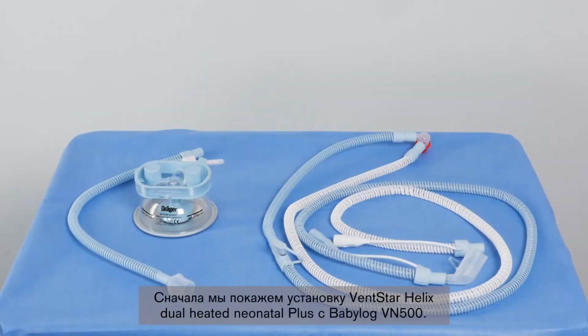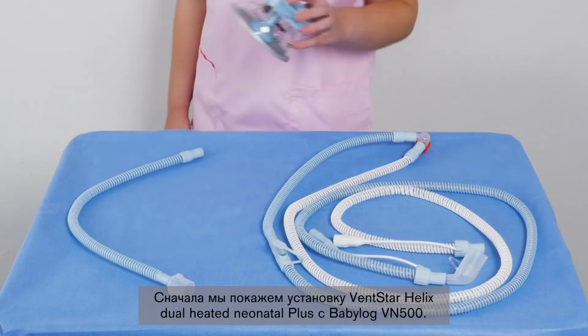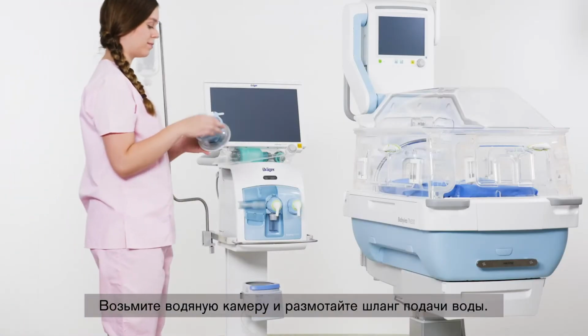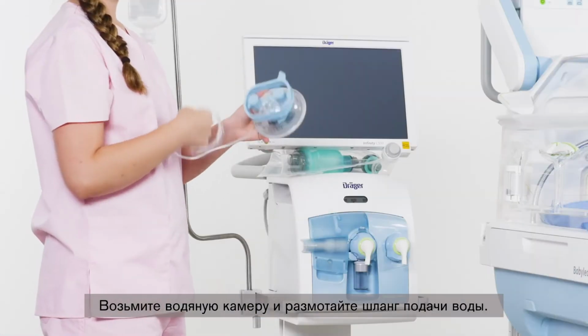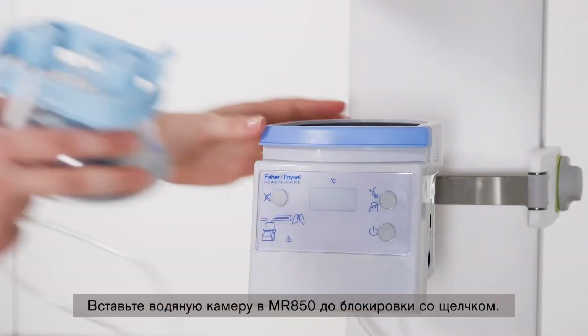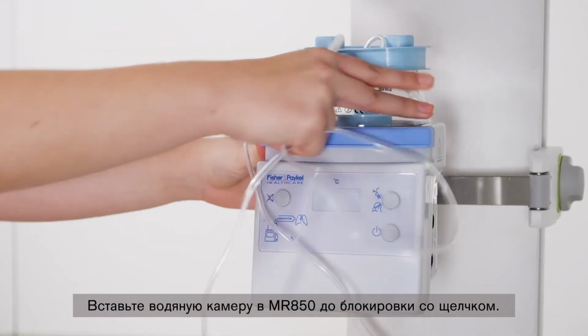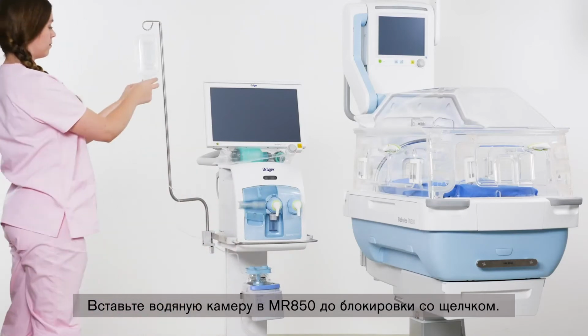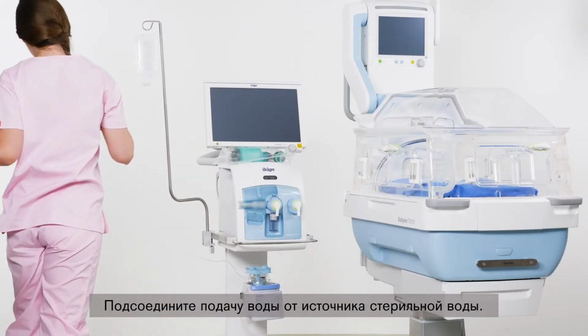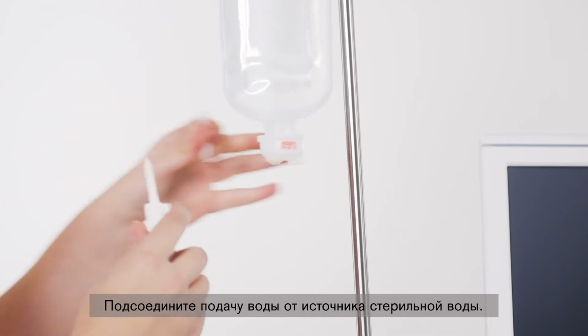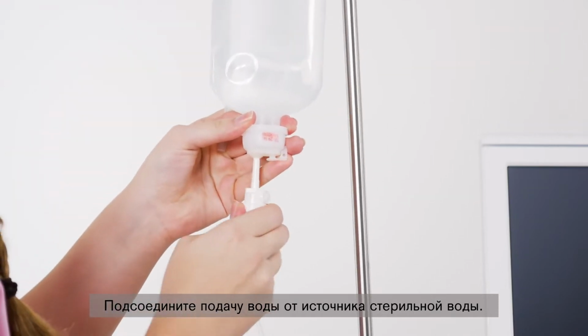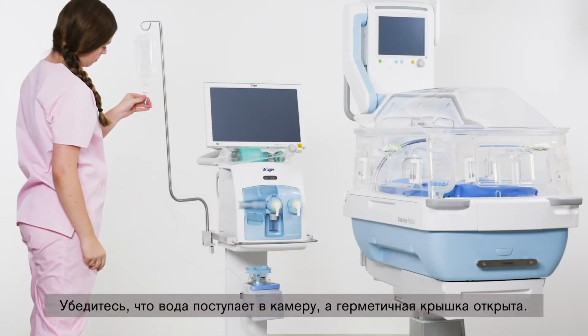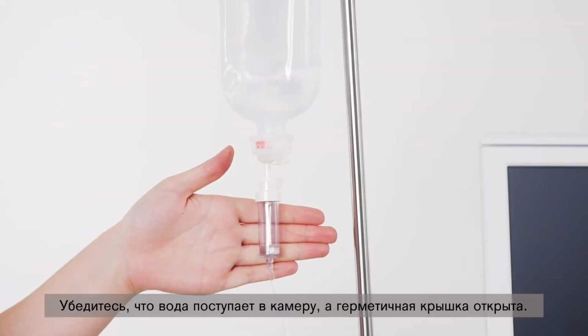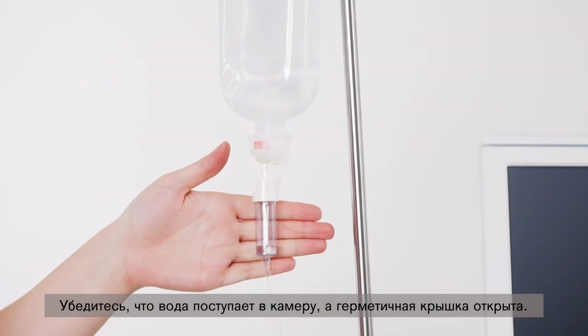First, we will show you the setup of the VentStar Helix Dual Heated Neonatal Plus with a Babylog VN500. Take the water chamber and unwind the water supply hose. Slide the water chamber into the MR850 until the interlocks snap into place. Connect the water supply to a sterile water source. Be sure that the water flows into the deaeration chamber and that the sealing cap is open.